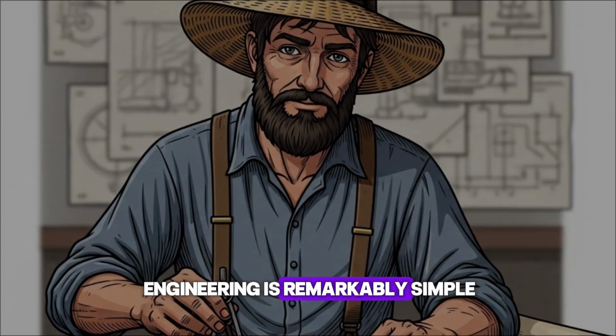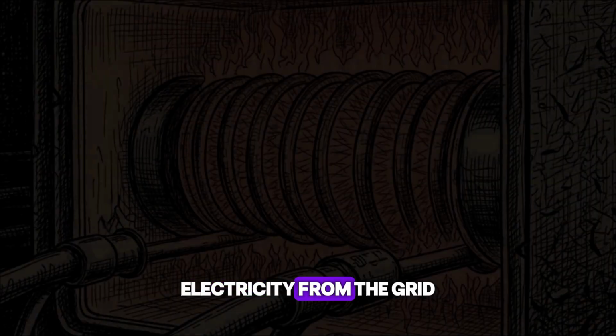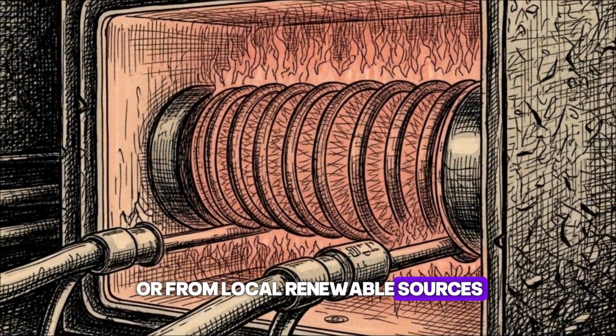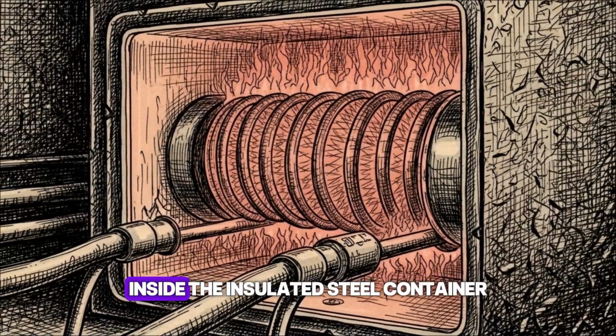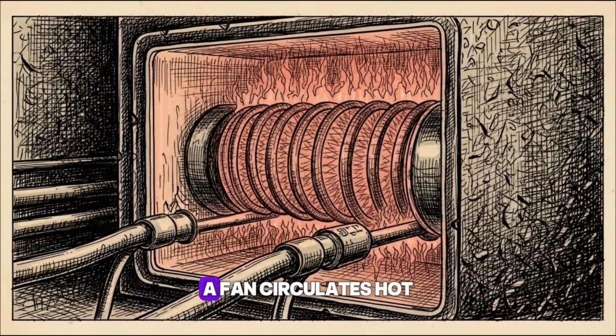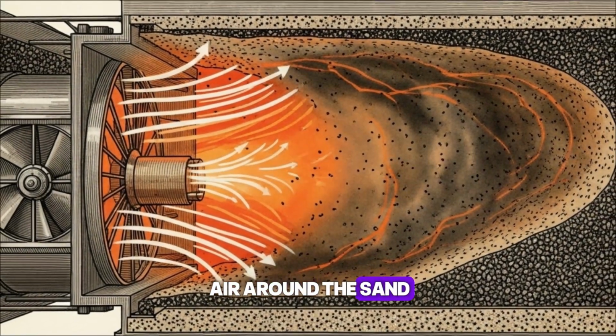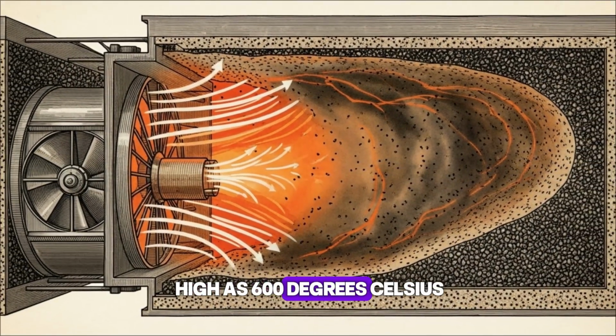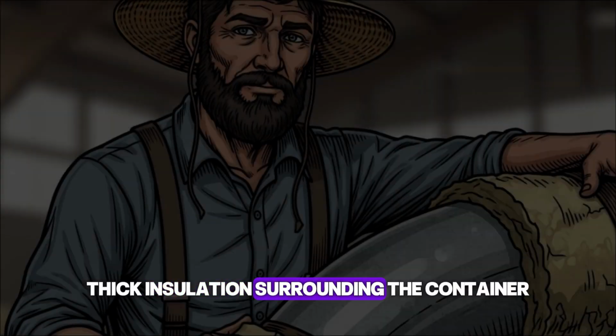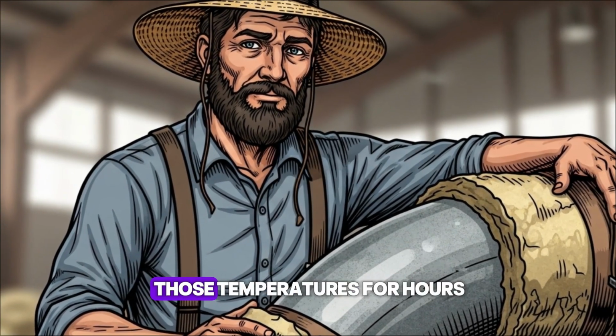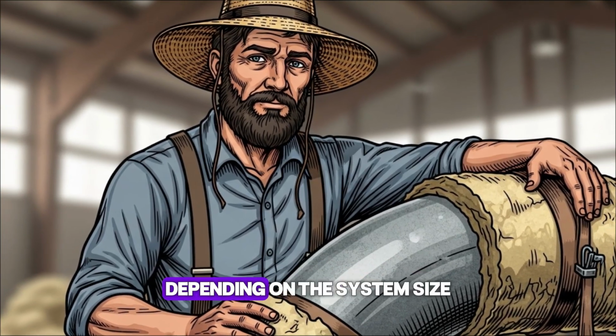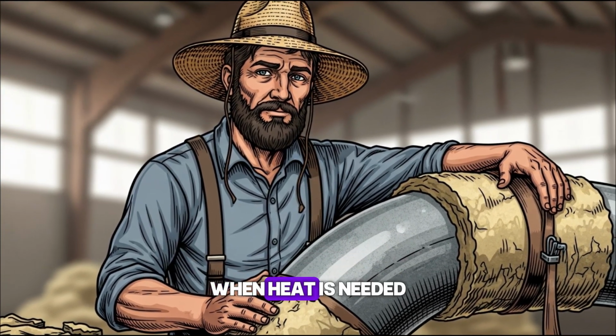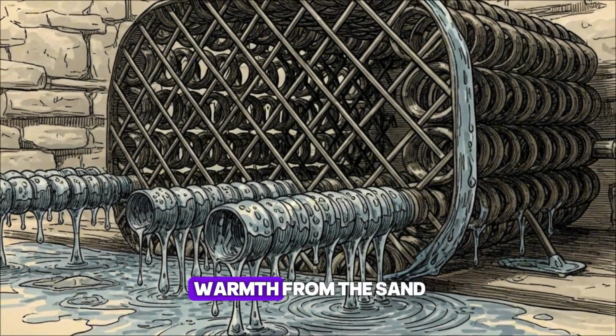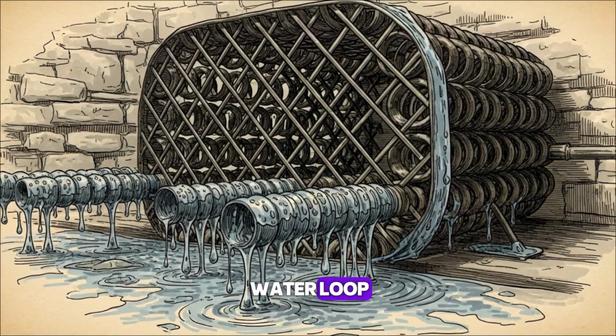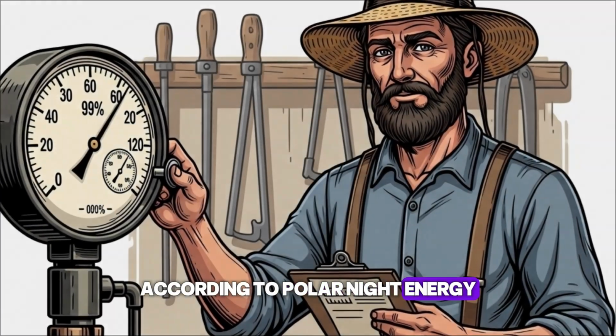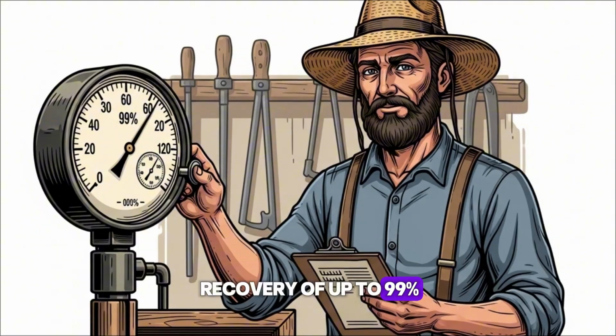The engineering is remarkably simple. Electricity from the grid or from local renewable sources powers a resistance heater inside the insulated steel container. A fan circulates hot air around the sand, heating it to as high as 600 degrees Celsius. Thick insulation surrounding the container keeps the sand at those temperatures for hours to months, depending on the system size. When heat is needed, a heat exchanger transfers warmth from the sand into the district heating water loop. According to Polar Night Energy, the system achieves heat recovery of up to 99%.